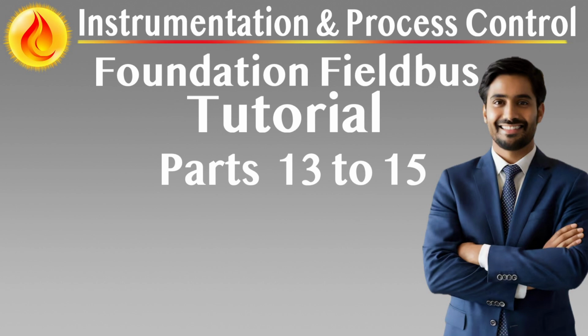Tagging, documentation, and addressing policies must be established during planning. Each Fieldbus device, block, and segment should have a unique, traceable identifier that aligns with plant standards. A consistent approach to node addressing, PD tags, and block indices will simplify commissioning, troubleshooting, and long-term support. Standard naming conventions for junction boxes, cables, and segment layouts are essential for field clarity.